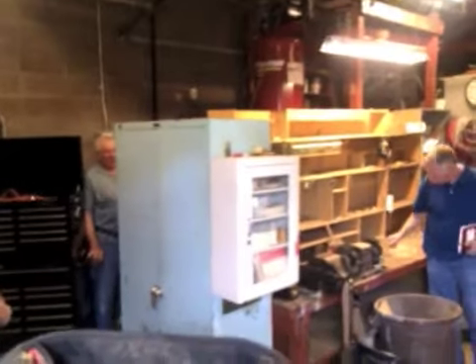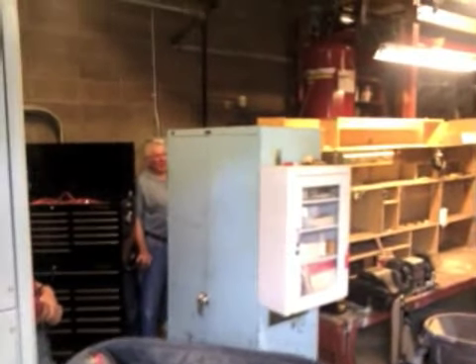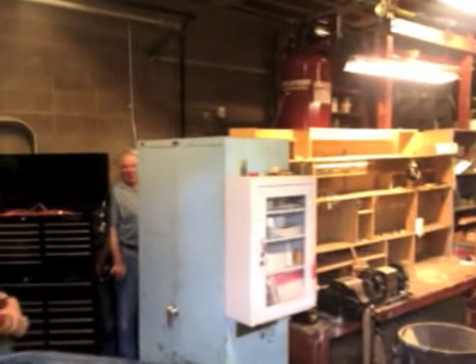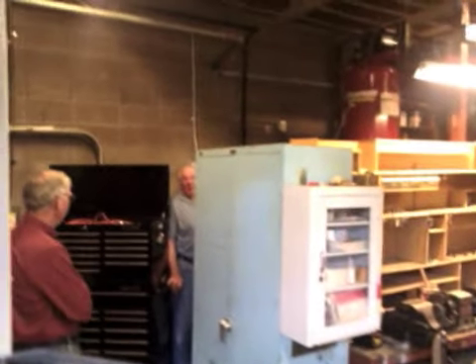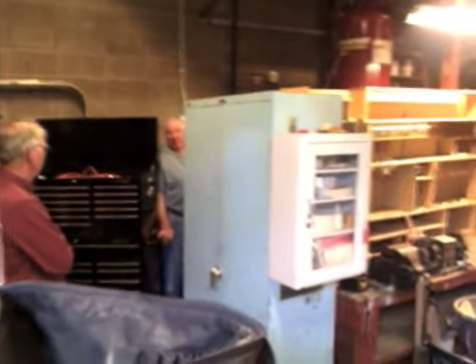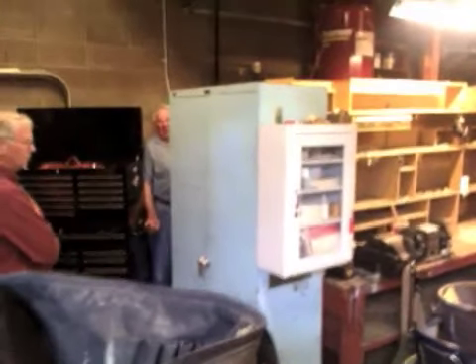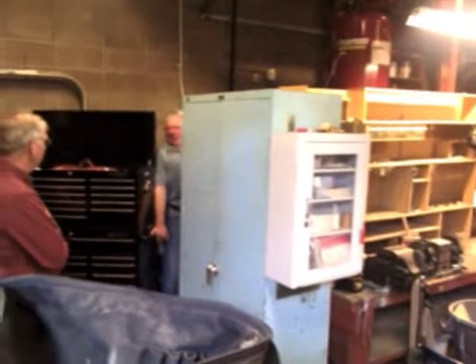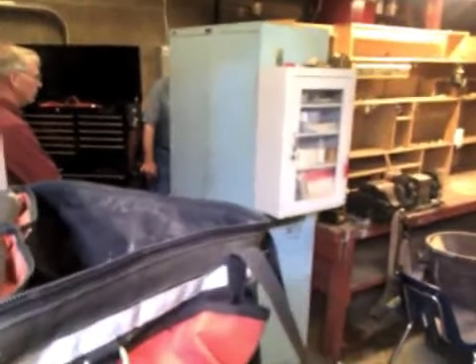As Dennis said, this is something that could close the school down. Does the heater also close the school down? Oh, it does. These are high priority. There's water hammer going on — the electric heat is only a small portion of the school, not even really a third of the whole school.